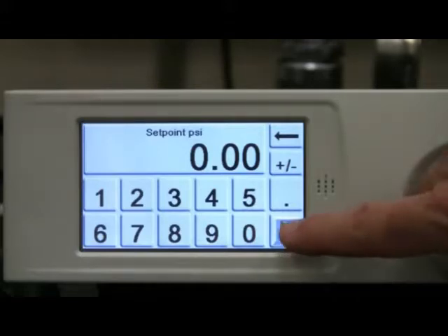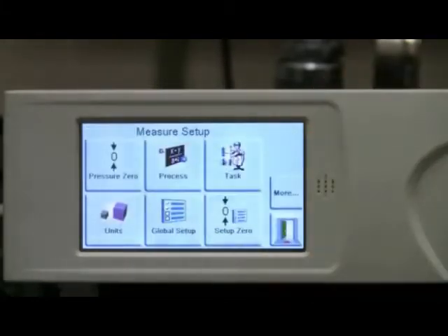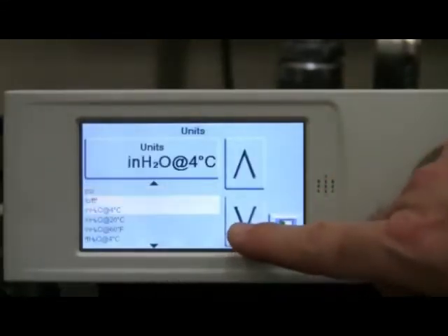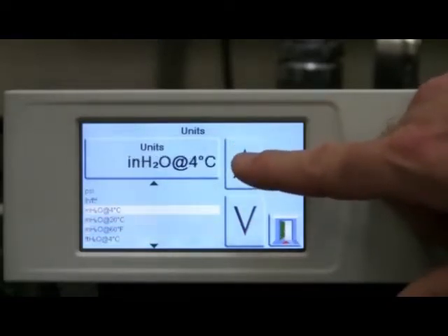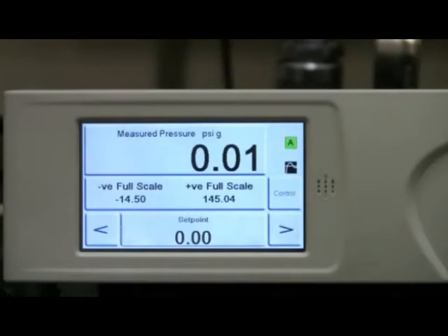Let's return to the main screen and perform a typical calibration run. Since the DPI-104 is presently displaying units in PSI, we will select PSI on the PACE 5000. PACE 5000 includes 24 different pressure units to choose from. If the required unit is not included, there are four user-defined units that can be created.